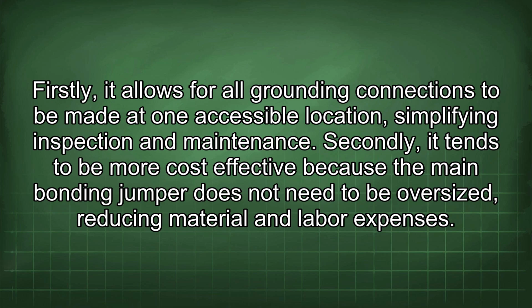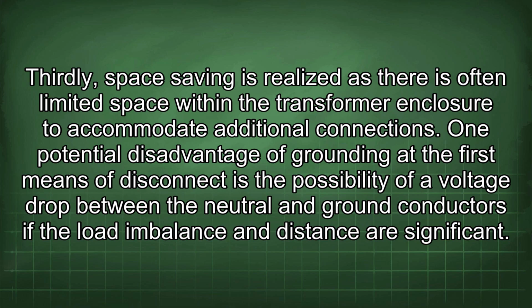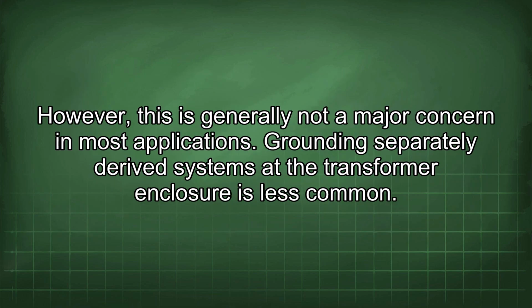Secondly, it tends to be more cost-effective because the main bonding jumper does not need to be oversized, reducing material and labor expenses. Thirdly, space saving is realized as there is often limited space within the transformer enclosure to accommodate additional connections. One potential disadvantage of grounding at the first means of disconnect is the possibility of a voltage drop between the neutral and ground conductors if the load imbalance and distance are significant.